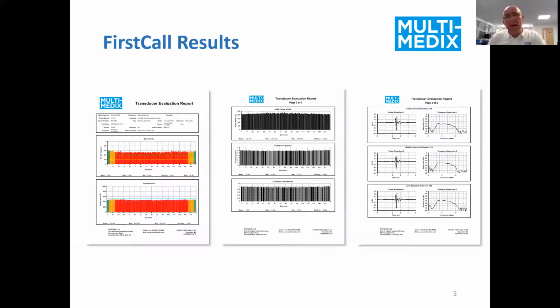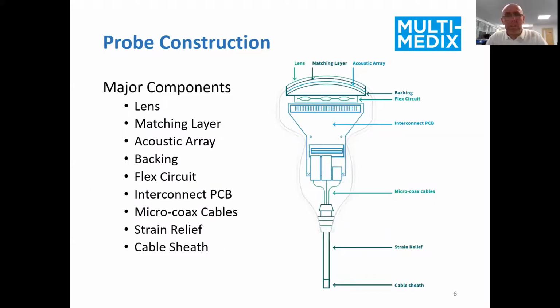So before we do that, I'm just going to do a little refresher in what makes up a probe for us. So our probe is made up of several components, and it doesn't matter whether it's in a linear configuration or a sector configuration or a curvilinear configuration like this diagram. So what we have is on the top facing the patient, we have our acoustic lens material, usually some kind of silicon membrane. Below that, we'll have the matching layers and actually acoustic array, which is the piezoelectric material, which transmits and receives the energy.